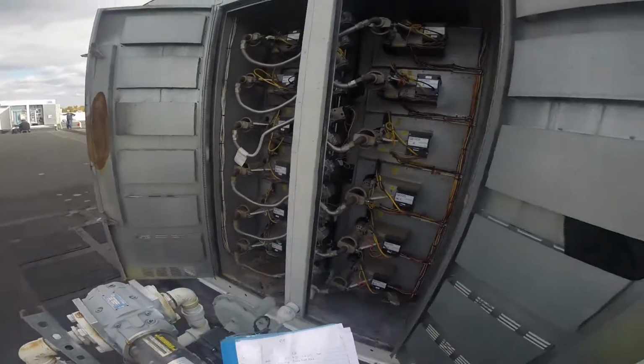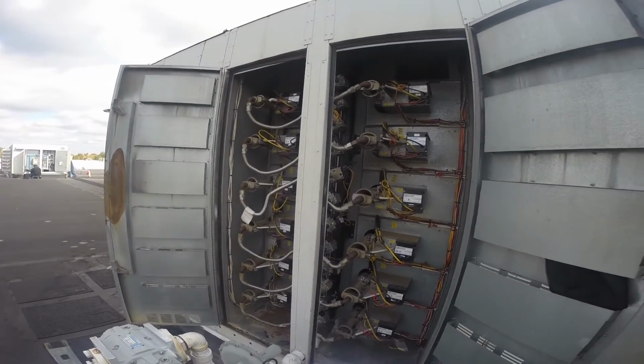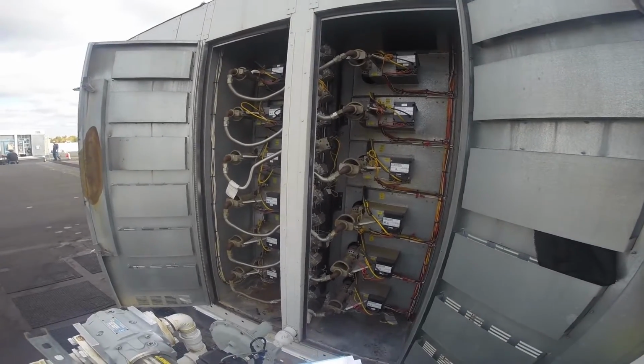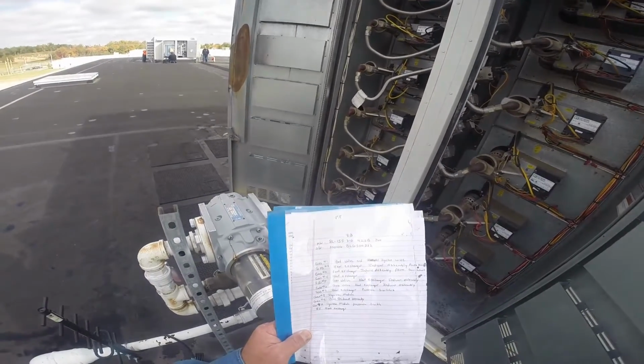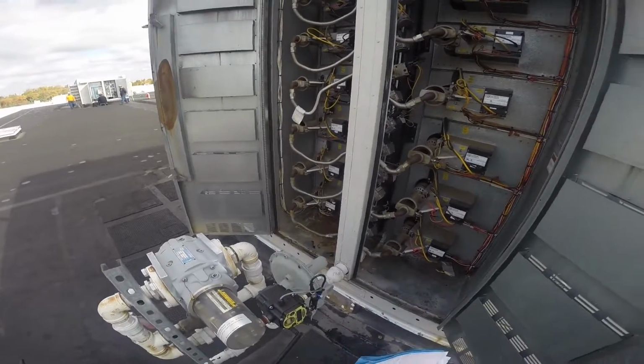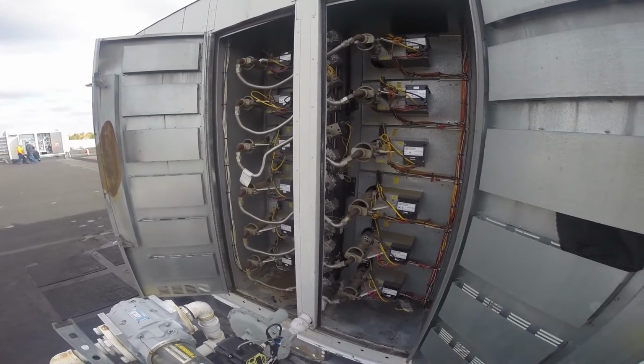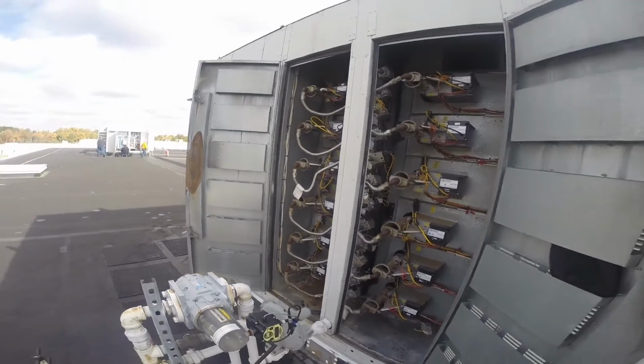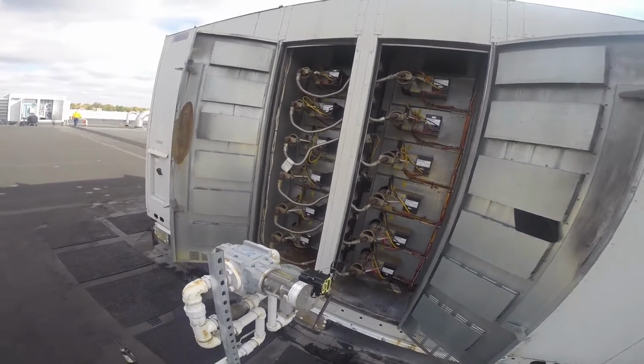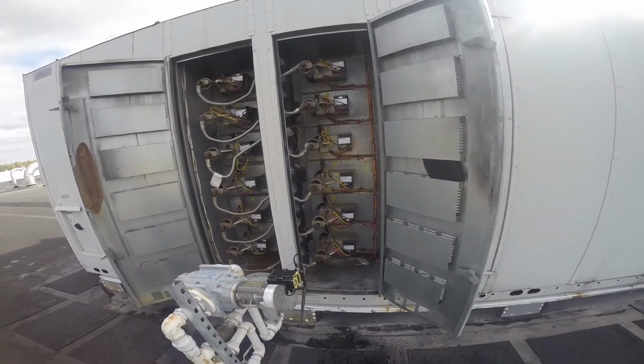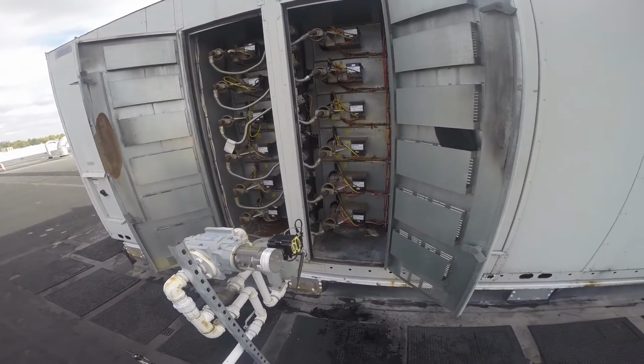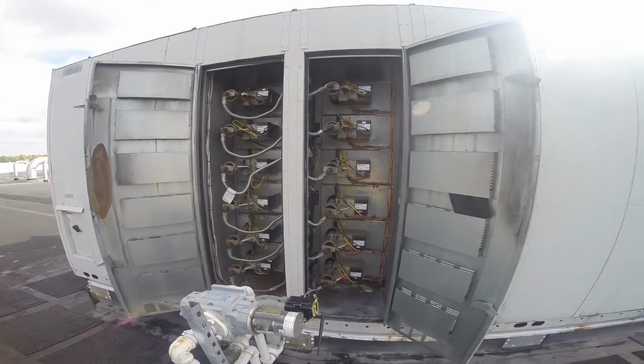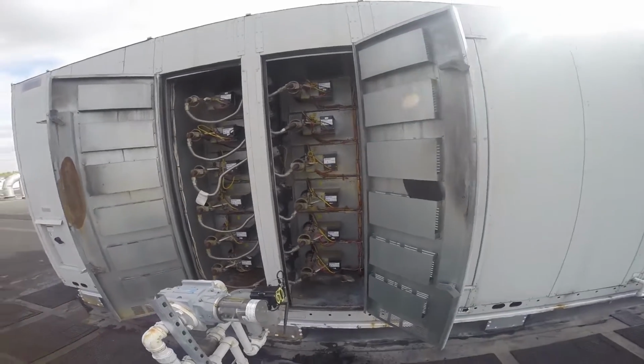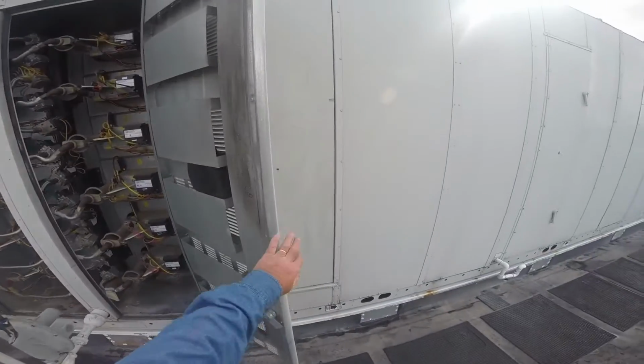Number 10 needs a new ignition module. It's not operating properly, and it's kind of weak on pressure also. Number 11, heat exchanger. We need to replace all the igniters, flame sensors, modules. My recommendation is just replace all the heat exchangers. If we're going to spend the time to tear it apart, we probably should just go ahead and change them. This door here would be on the inlet side of the heat exchangers.